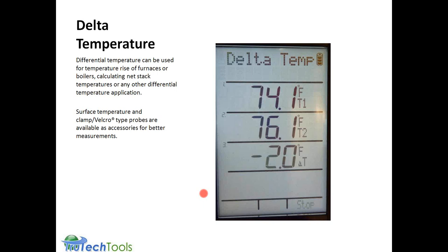The delta temperature screen allows you to measure any types of differences in temperature. Here, the little probe in the cage at the bottom is one socket. Underneath it is one socket for the temperature probe. And then whatever's connected to the flue gas probe connector is the other one. In this case, you pretty much need to have the adapters to do it, or an accessory probe to conduct this measurement. There is a temperature probe adapter that would screw into the flue gas fitting. And these are custom probes from Testo with a special fitting on a circular type connector that goes in. If you're interested in that, you can either drop us a line or give us a call, and we can present that information to you about accessory probes for differential temperature measurement.